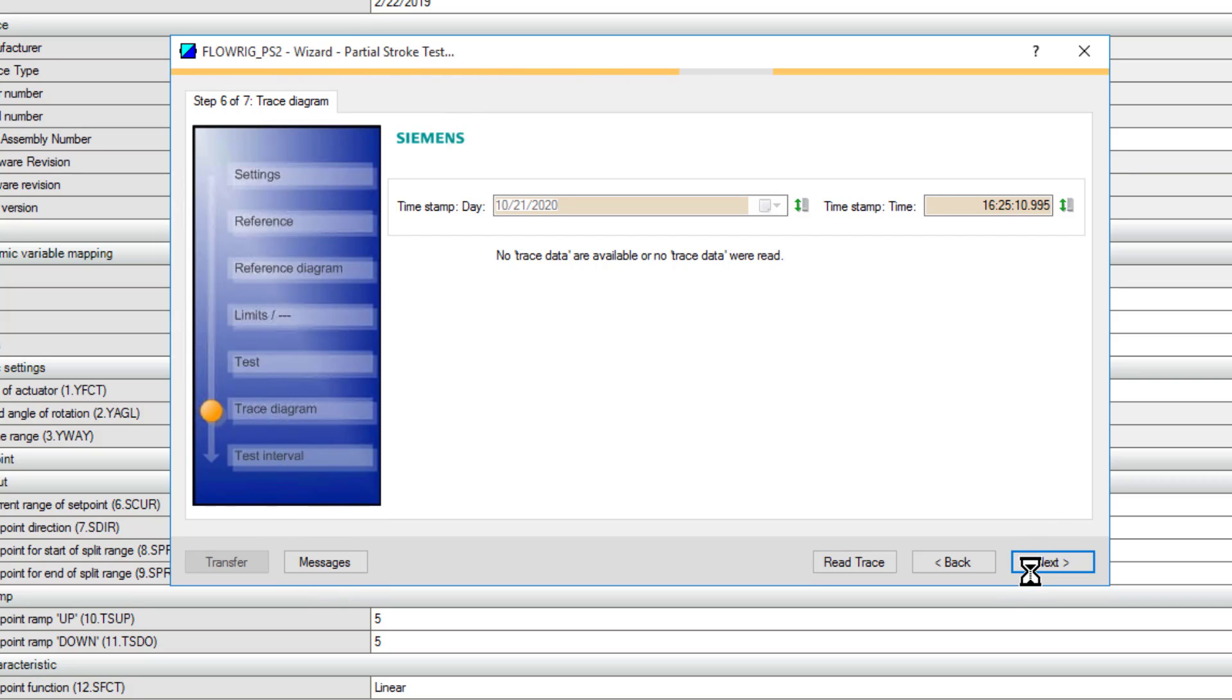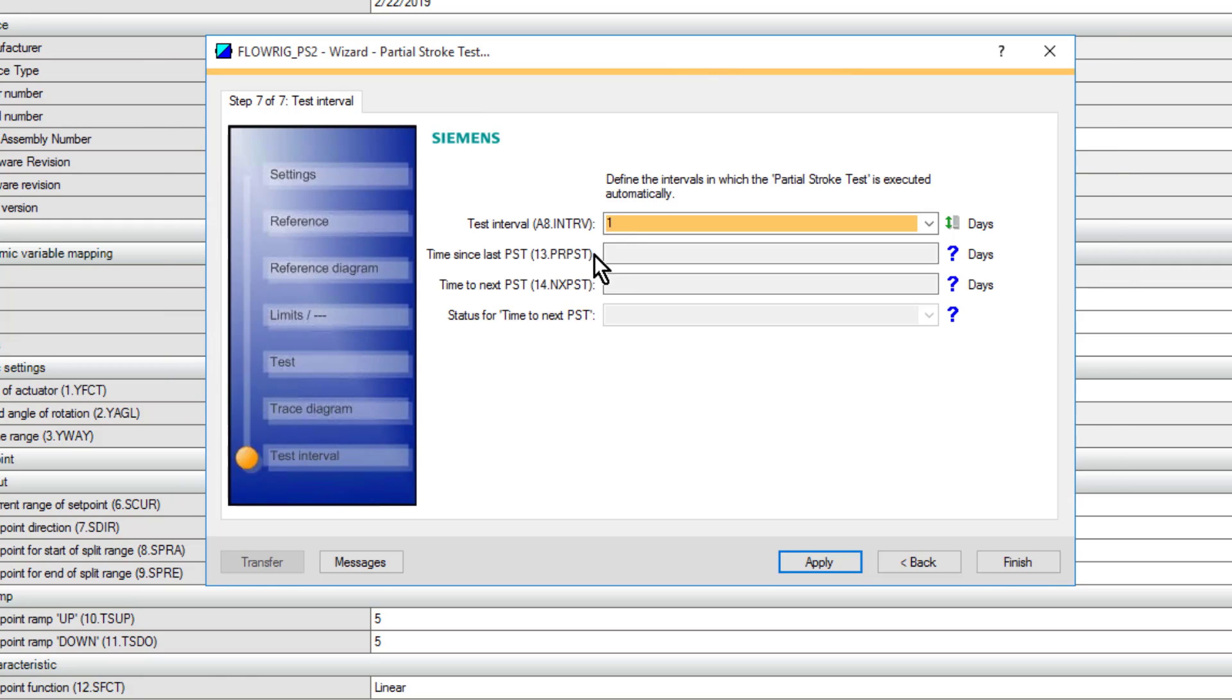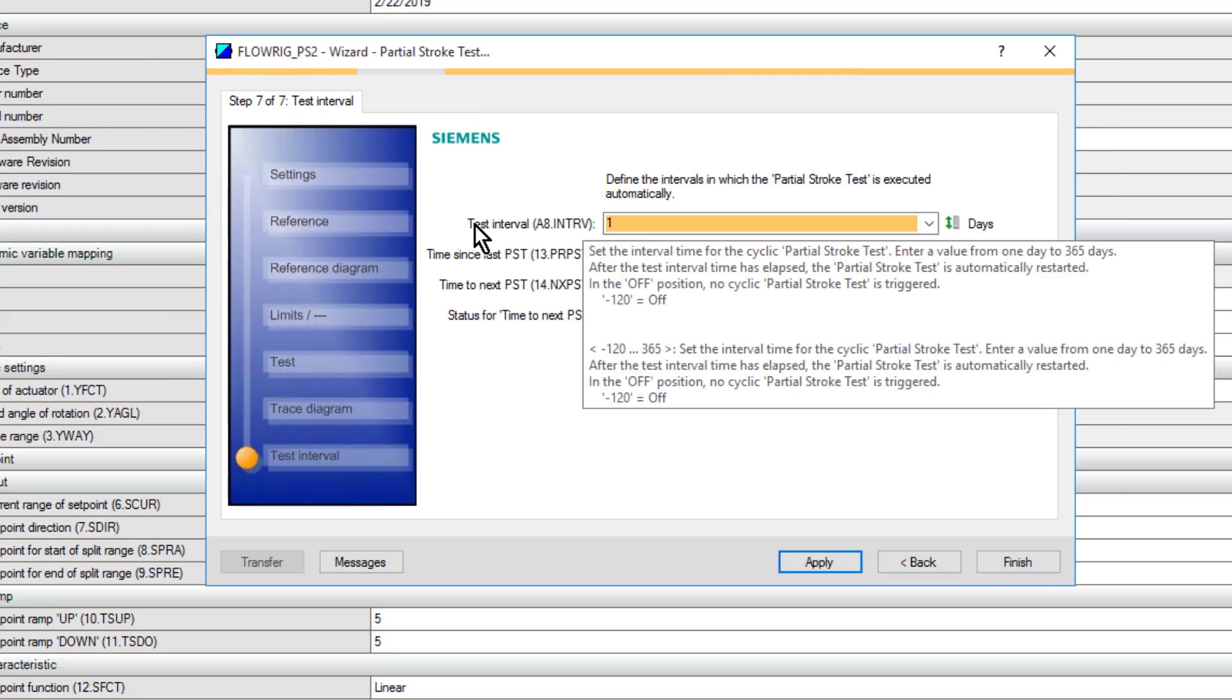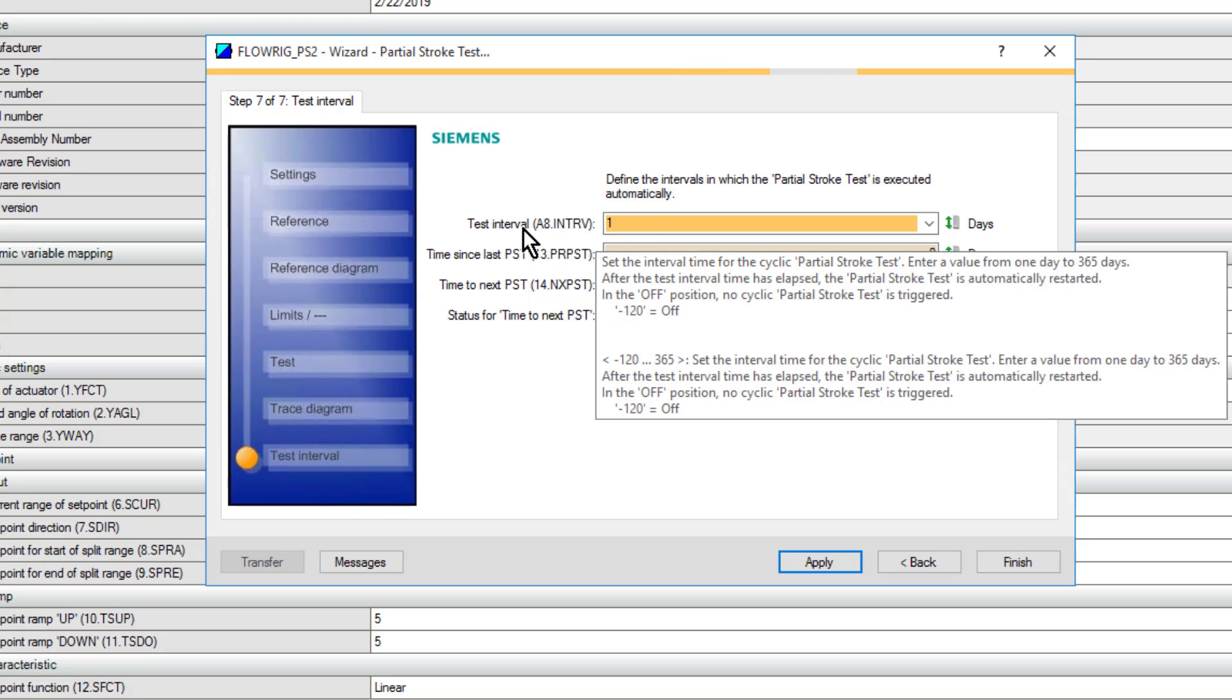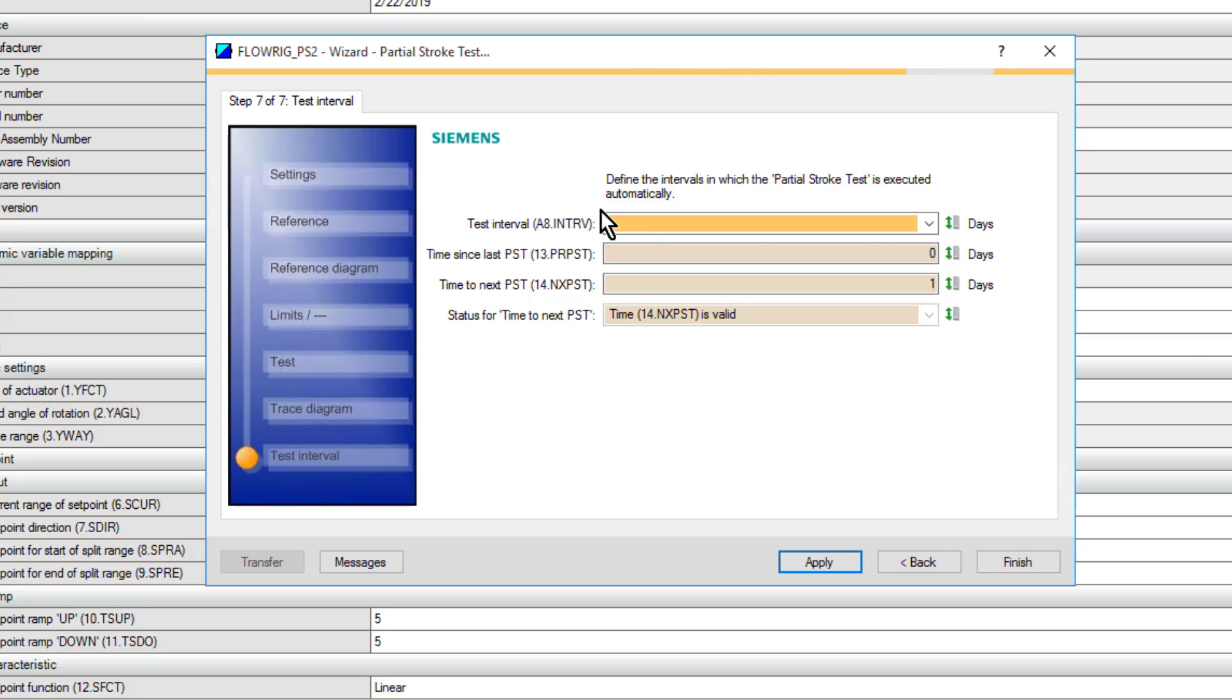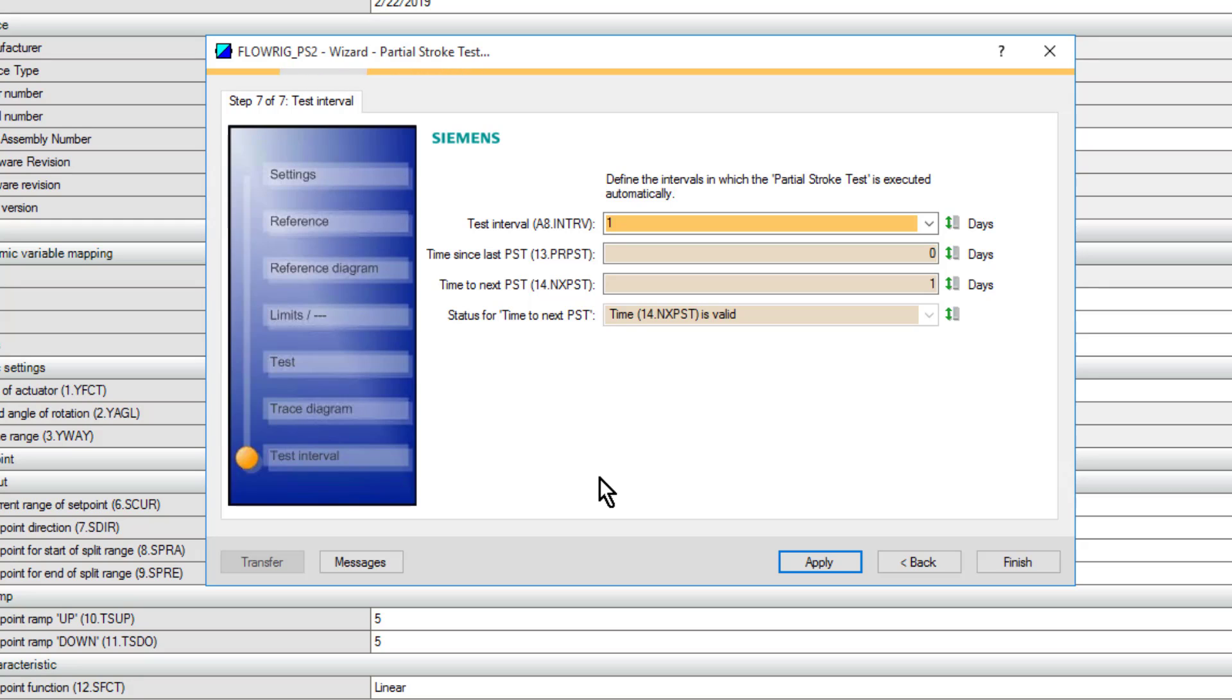Here we have the interval for the partial stroke test. I've set this to do it every day, and your valve needs to be within the percentage limit that you've specified in your settings. If you remember back, I said that my start position is 100%, and the tolerance on that was either 5 or 10%. If it's outside of that tolerance, it will not start the partial stroke test. I'll click finish.